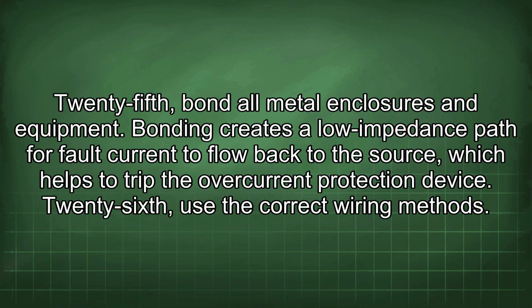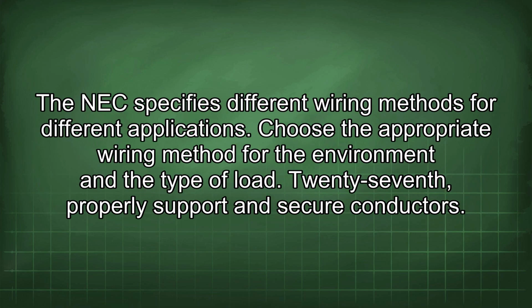25th, bond all metal enclosures and equipment. Bonding creates a low impedance path for fault current to flow back to the source, which helps to trip the overcurrent protection device. 26th, use the correct wiring methods. The NEC specifies different wiring methods for different applications. Choose the appropriate wiring method for the environment and the type of load.